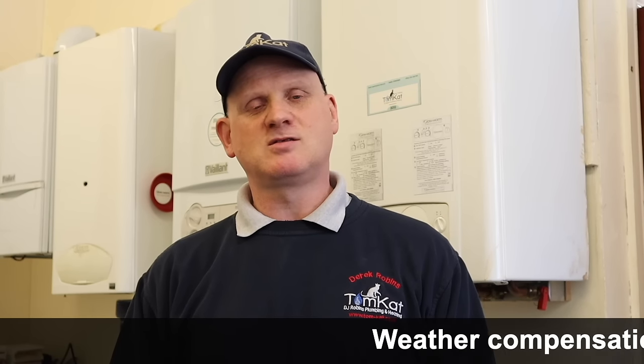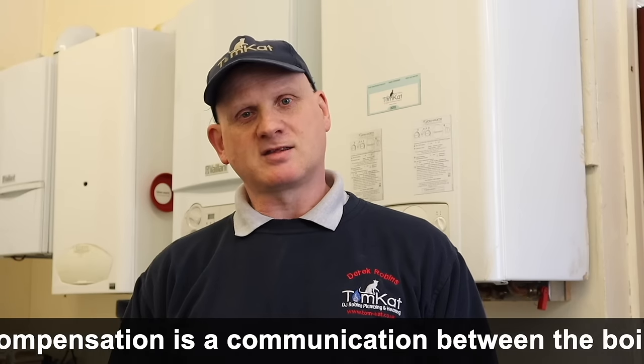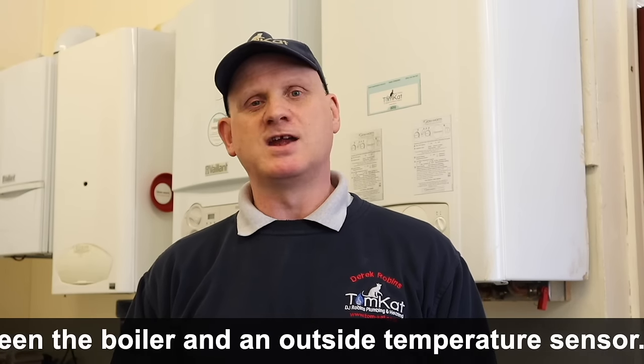The other big barrier to achieving this factory setting of efficiency is the introduction of the central heating controls. Now, for a combi boiler, the best heating controls you can ever fit will be the controls from the manufacturer, in my opinion, because these controls will be able to speak the language of the boiler and run the boiler at its most efficient. We would all be forgiven for thinking that by investing in smart controls, we would be benefiting from greater efficiencies. However, maximum efficiencies on boilers will only be achieved when the boiler is connected to weather compensation. That means a stat that is telling the boiler what the temperature of the outside is.